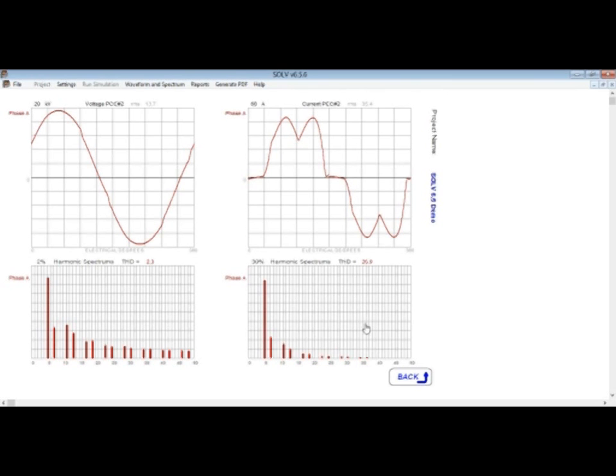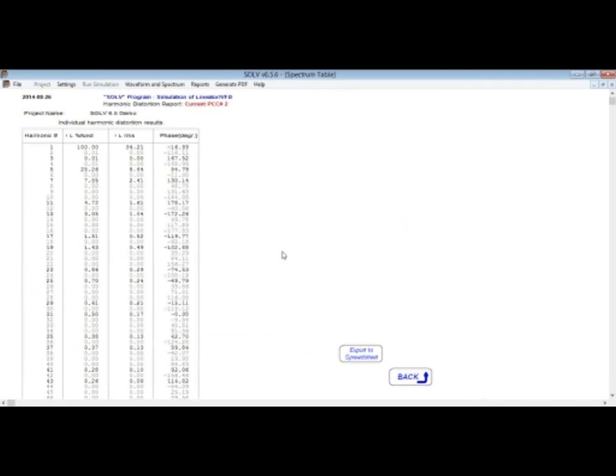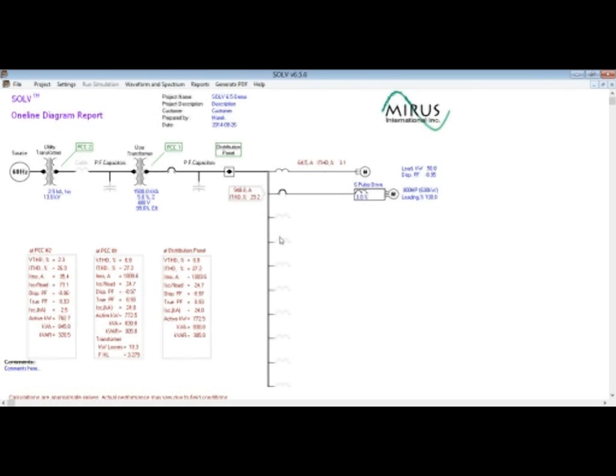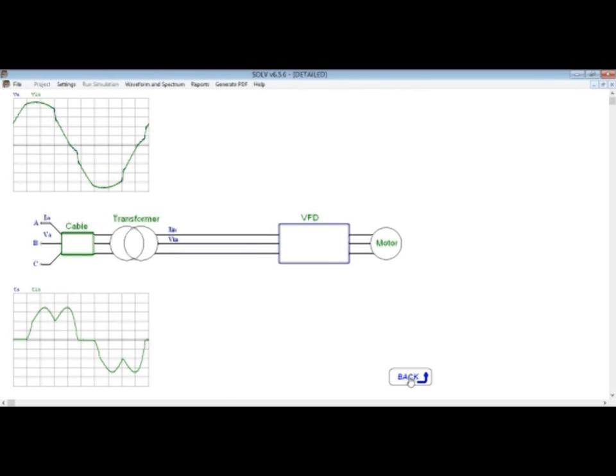Moving the cursor in the area of the harmonic spectrum, you can see the selection hand appears. This usually indicates that this is an area where you can click. So by clicking here, another window opens with the individual harmonic distortion results, and this can be exported to an Excel spreadsheet for future use. So going back, we can also view waveform and spectrum for PCC1 and distribution panels, and also available for branch drive.